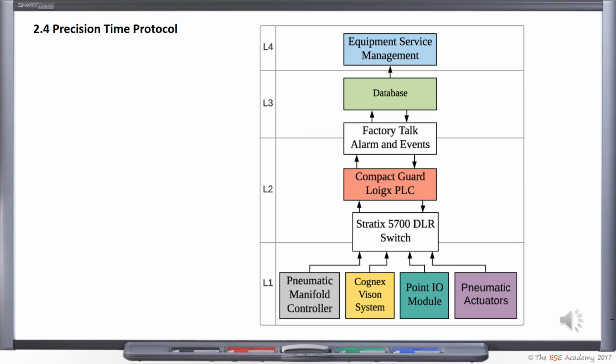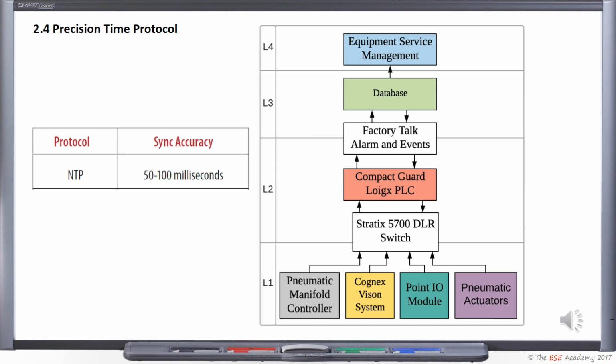To timestamp events, a time synchronization protocol can be used. Traditionally, NTP is the most commonly used protocol, which works well on LANs and WANs. However, many NTP clients run on non-real-time operating systems, such as Windows. NTP protocol accuracy cannot be guaranteed. Clock corrections of 10 to 15 milliseconds are common.